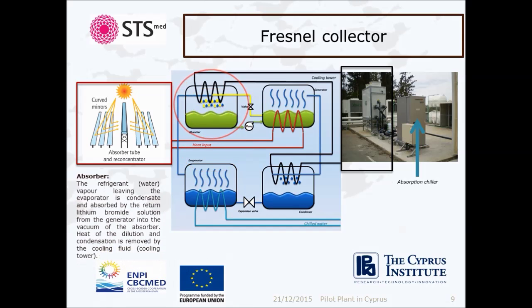An absorption chiller like the one installed at the Cyprus Institute has 4 chambers. First, the absorber. The refrigerant vapor, meaning water vapor, leaving the evaporator is condensed and then absorbed by the lithium bromide solution from the generator into the vacuum of the absorber.